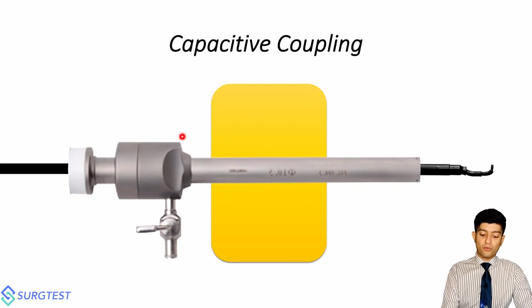All of our laparoscopic instruments have an inner conducting core with an insulation on the outside, and the tip is always uninsulated because this is where you want all of the energy to be delivered. When you pass these laparoscopic instruments through a metal trocar, you are essentially creating a capacitor of sorts. One end of the capacitor is a metal trocar, the other end is the inner core within the laparoscopic instrument, and the non-conducting sandwiched area is the insulation on the laparoscopic instrument that you can see over here. I hope that is clear. The creation of this capacitor though does not cause too many issues. It can hold charge, but because the laparoscopic ports are going through the body wall, the current density is never high enough when the energy is dispersed to actually cause the patient any significant problems.